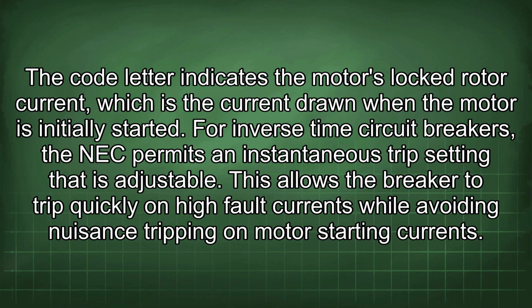The code letter indicates the motor's locked rotor current, which is the current drawn when the motor is initially started. For inverse time circuit breakers, the NEC permits an instantaneous trip setting that is adjustable. This allows the breaker to trip quickly on high fault currents while avoiding nuisance tripping on motor starting currents.